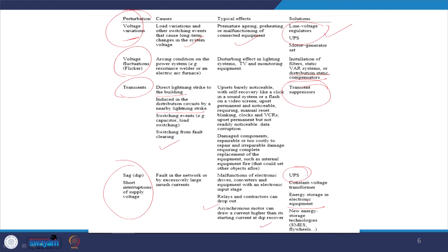Thereafter, you have voltage sag, from a fault in the network or an excessively large inrush of current, and that is what it will do. It will cause malfunctioning of a lot of electronic devices, converter equipment with electronic input; relays and contactors can drop out; an asynchronous motor can draw a current higher than its starting current as it dips and recovers. Here also you require an uninterrupted power supply, constant voltage transformer, energy storage in electronic equipment. It may be an ultracapacitor; a new energy storage system such as SMES and the flywheel can be the solution for the intermediate sag control.